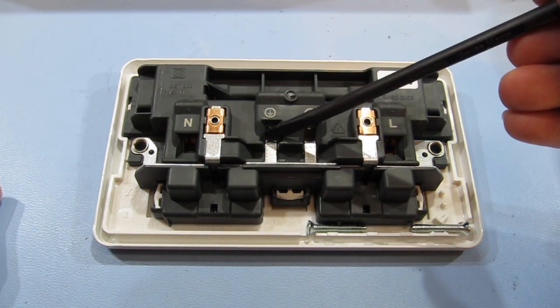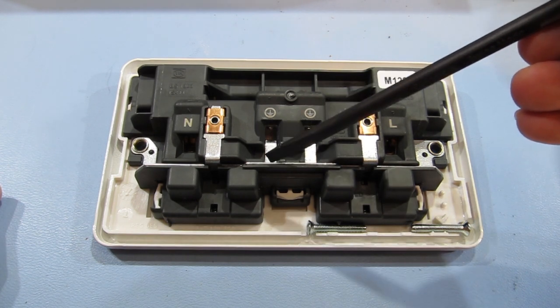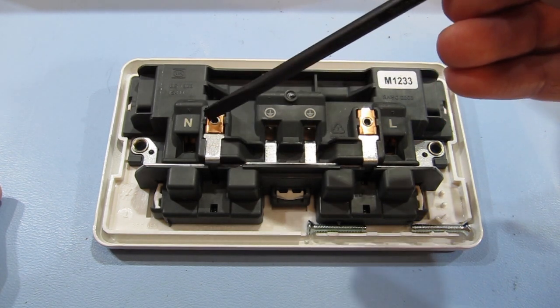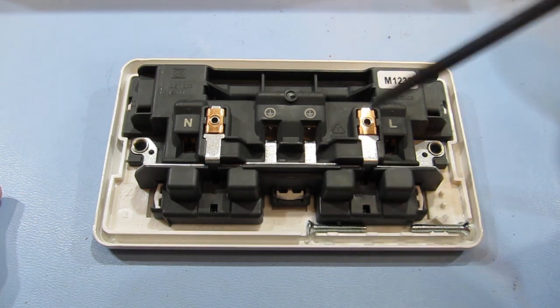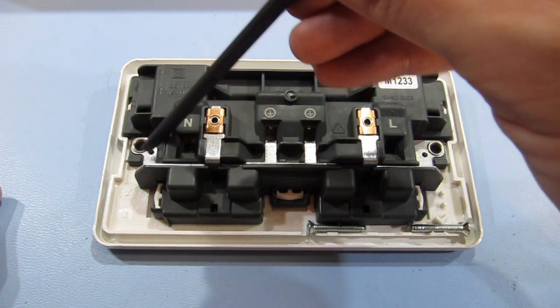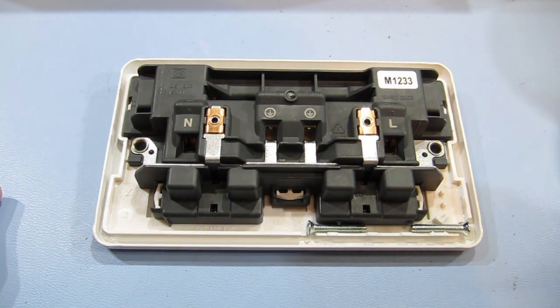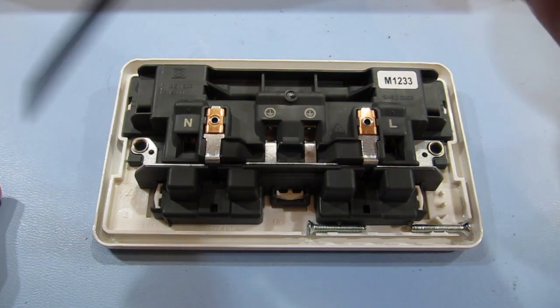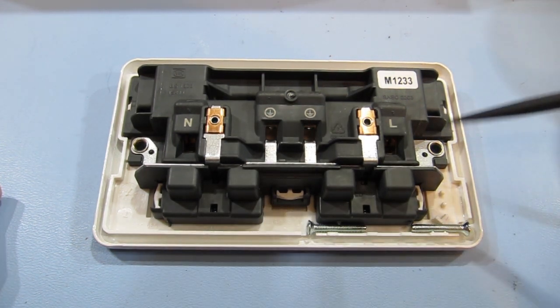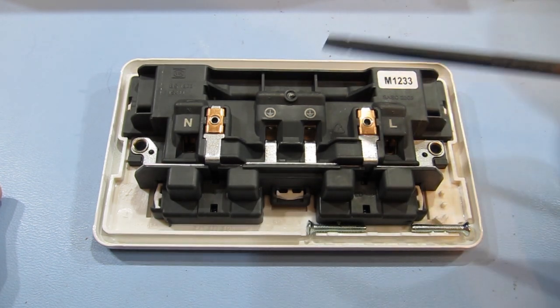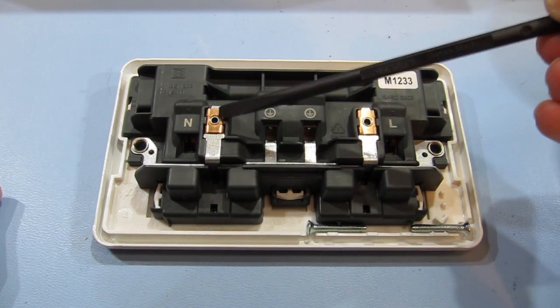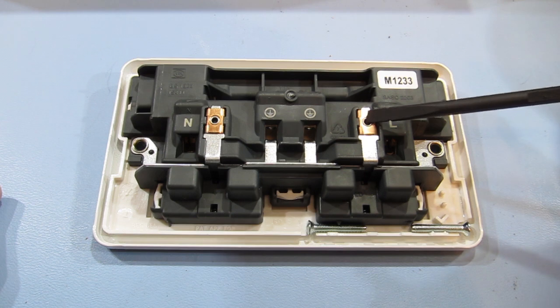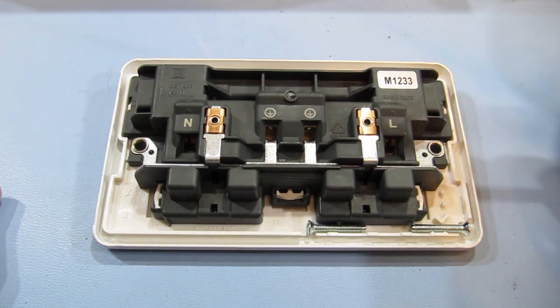And you can see that the earth terminals are connected via a strip to the earth connection on the actual socket, but then also to the lugs where the screws go through to normally earth the metal pattress that would be in the wall as well. But obviously I want to be able to isolate the mains earth from these sockets, but I still do want protection on the transformer case from becoming live.